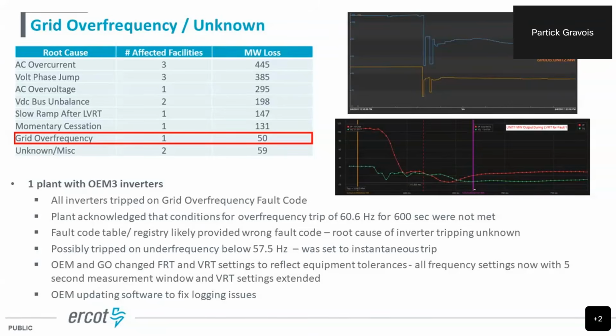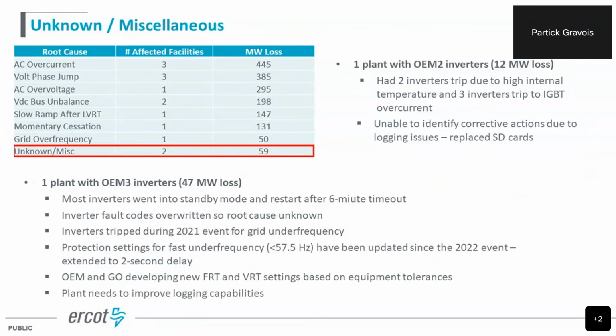So hopefully we won't be seeing any more issues with this facility as well. Again, kind of the same thing with one on the bottom, another plant with the OEM3 inverters had a 47 megawatt loss, and they weren't really able to identify the root cause. They had their inverter fault codes overwritten by the PPC. So they've gone through the same process, extending out the FRT and VRT requirements, and they've done some work to improve their logging capabilities so they're not overriding these fault codes.